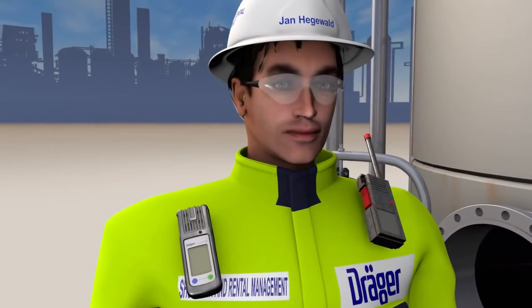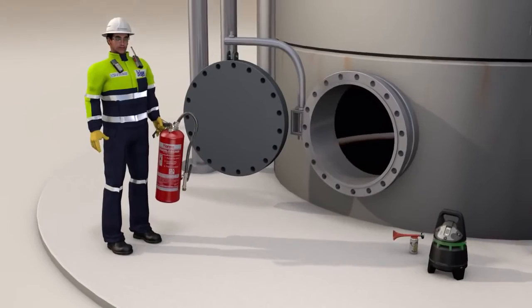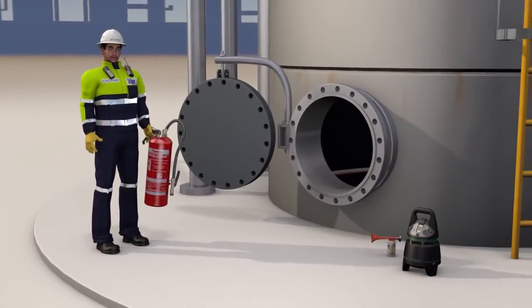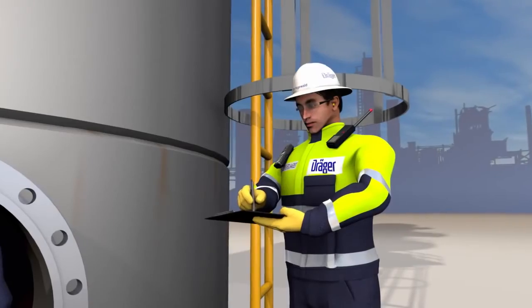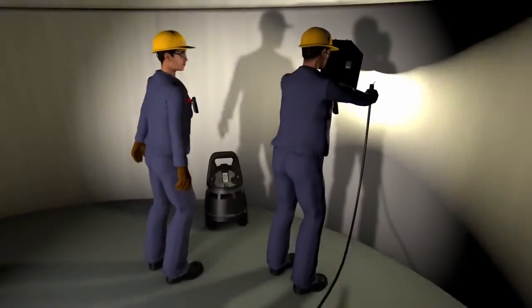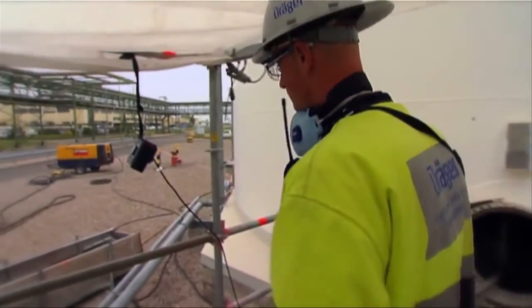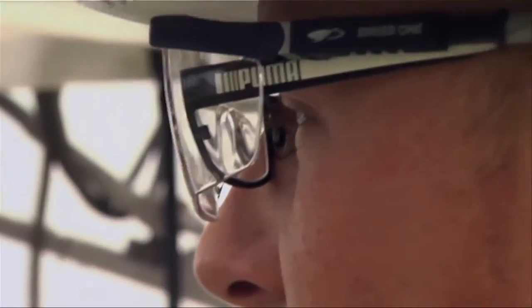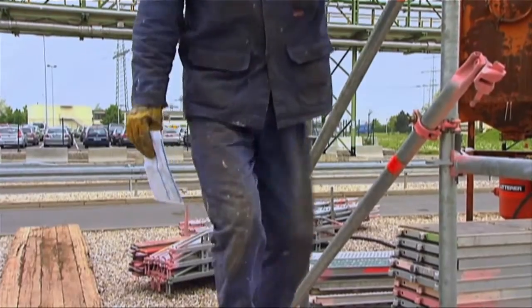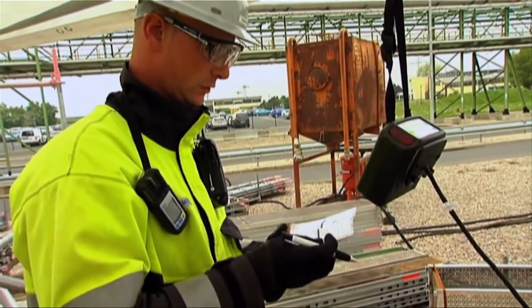The first safety officer takes over his work area and is provided with the following standard equipment. As well as a fire extinguisher, the safety officer is equipped with a gas detector and a horn for sounding the alarm. The safety officer checks the access permit and removes the no entry sign. It's only now that the contractors are allowed to access their workplaces. Before a contractor starts work, the safety officer first checks his permits. The time, the worker's name and measured values are likewise documented.